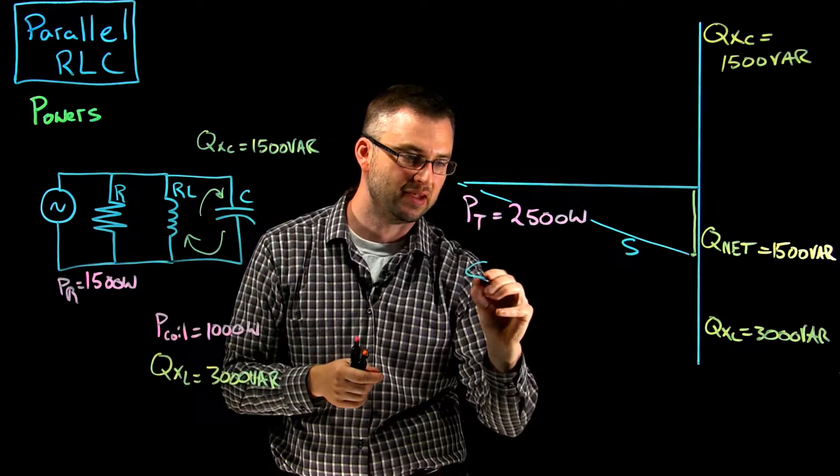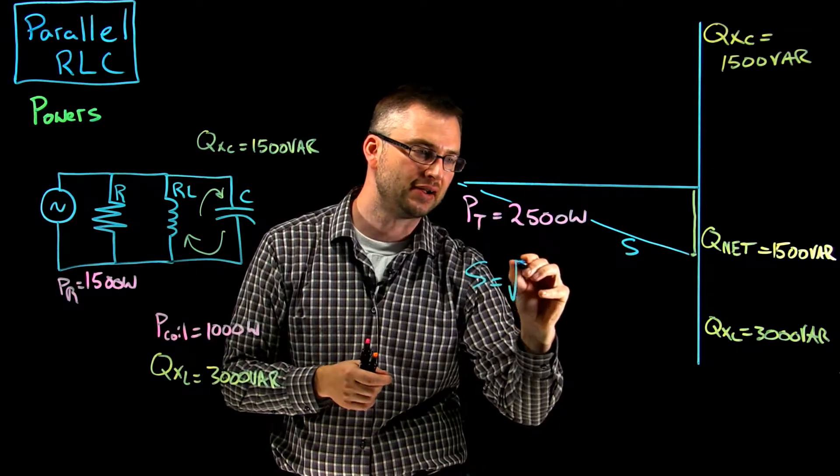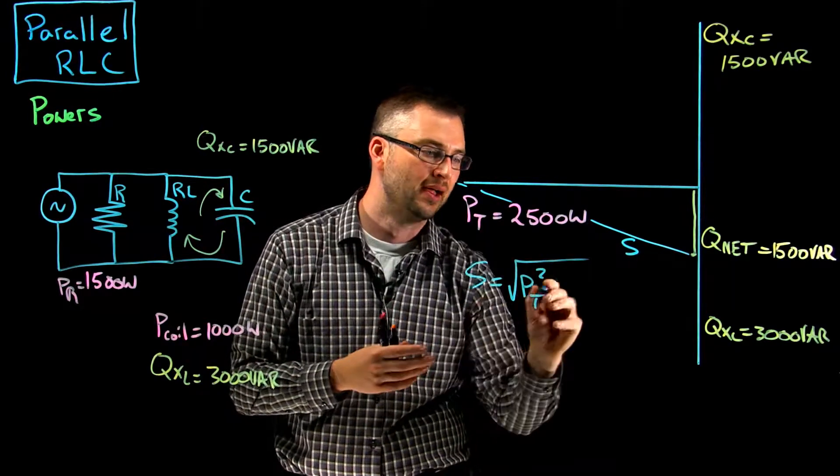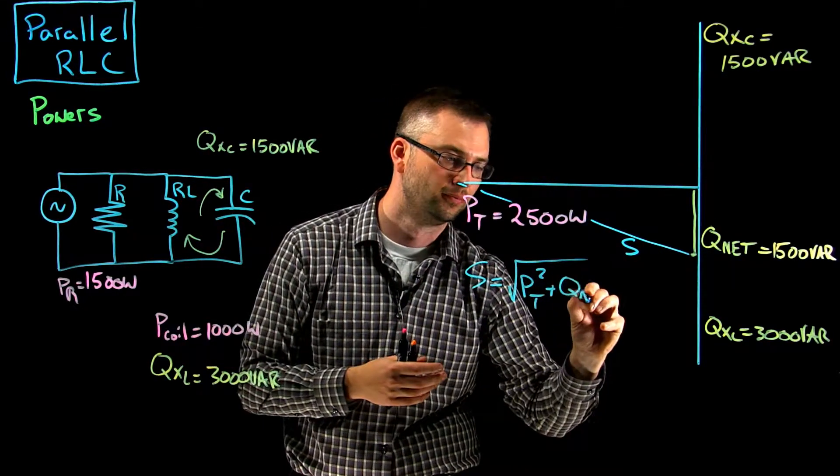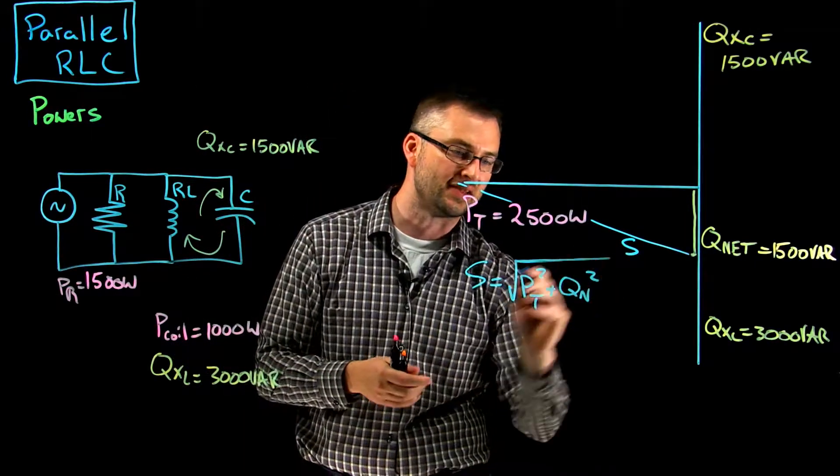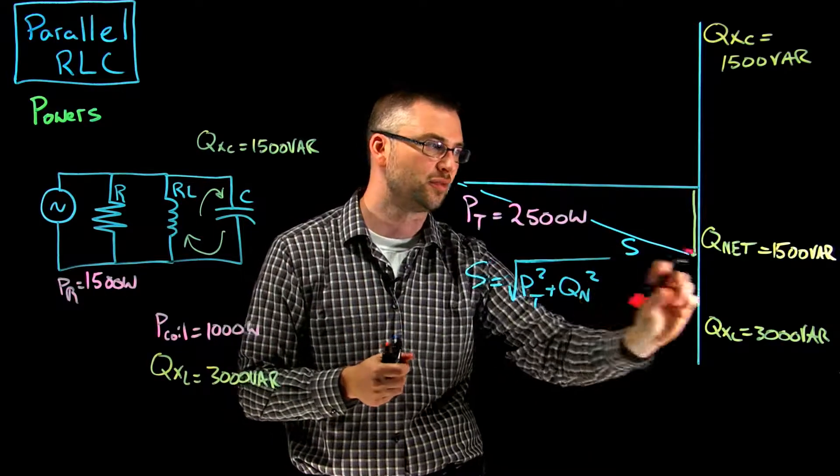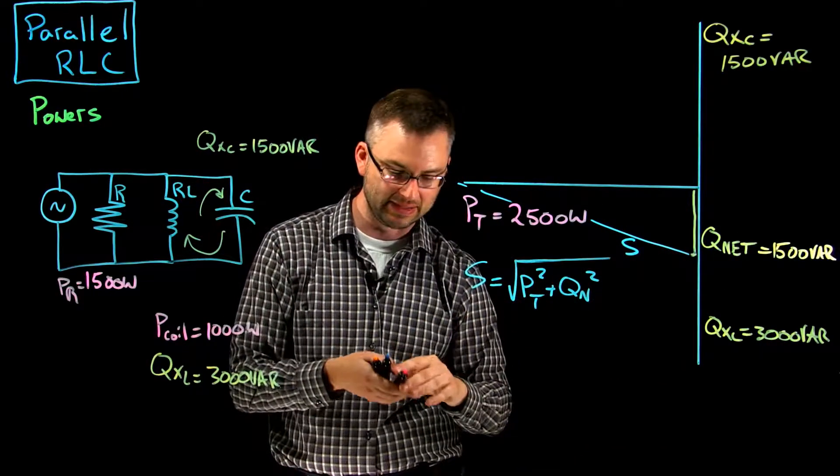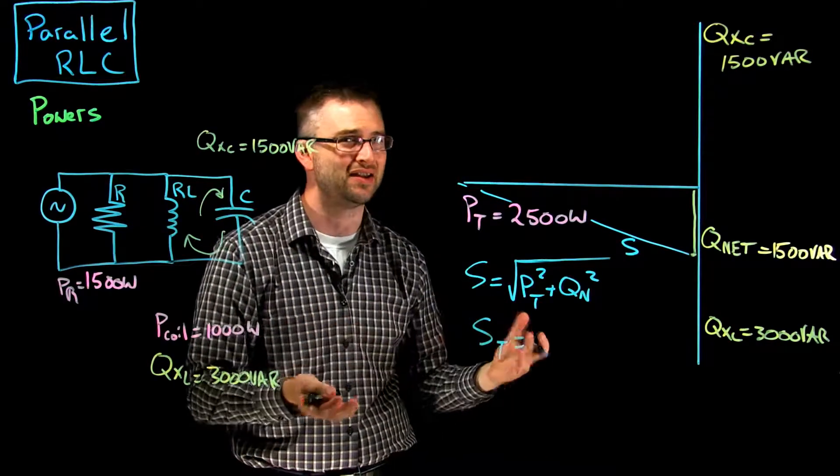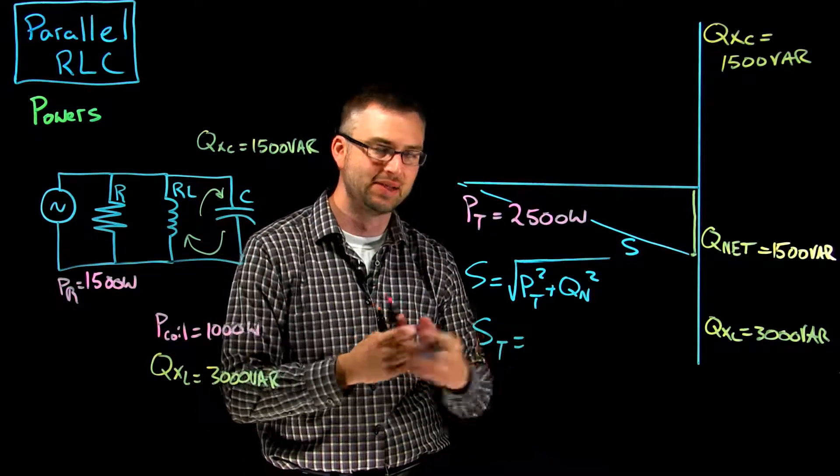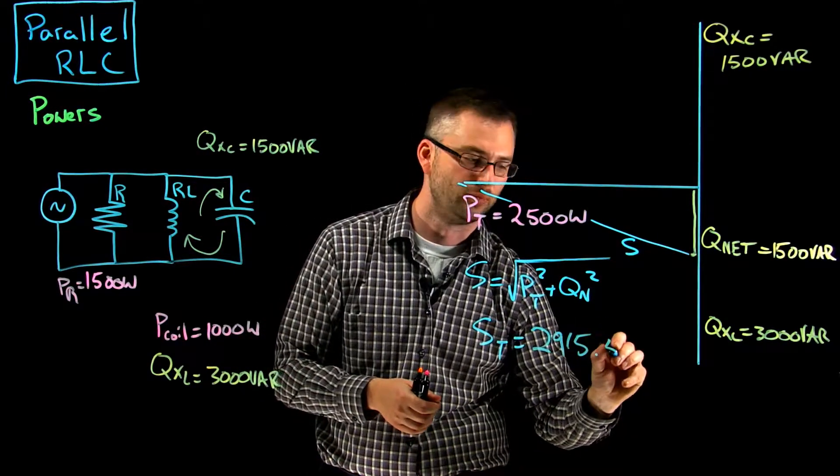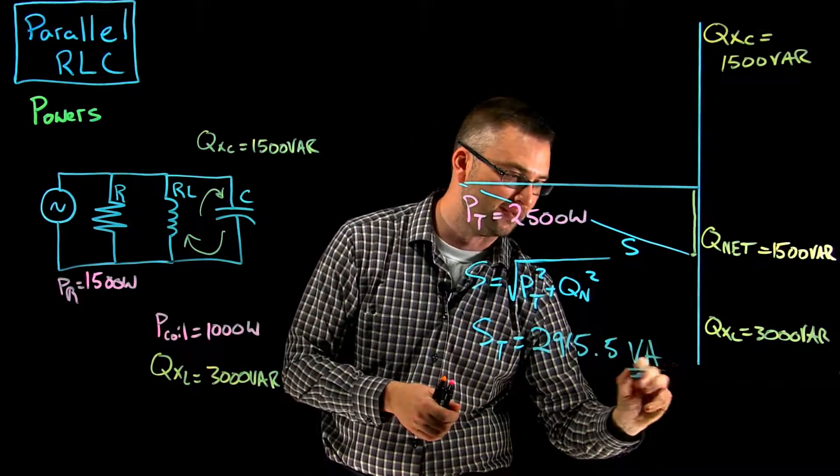So the S is going to be the Pythagorean theorem product of power total squared plus my Q net squared, take the square root of that, and we'll solve for the S total. So we do that, punch those numbers in, 2500 squared plus 1500 squared, and I get an S total, and S is kind of defined as a total of the circuit, but my S total will be 2915.5 VA.